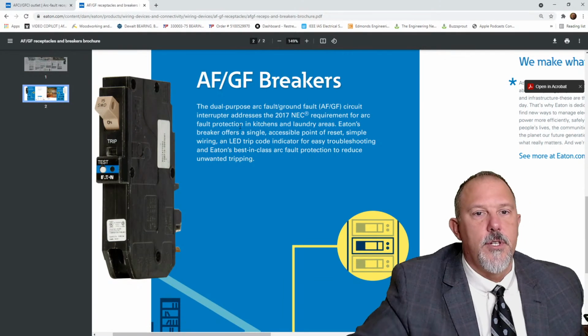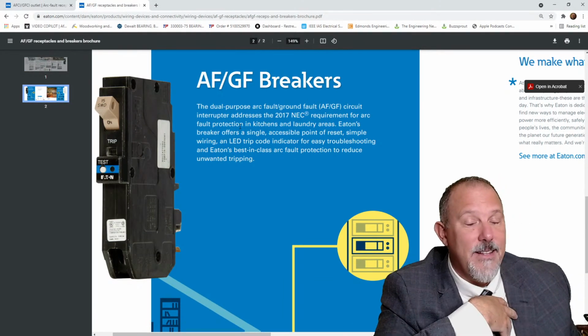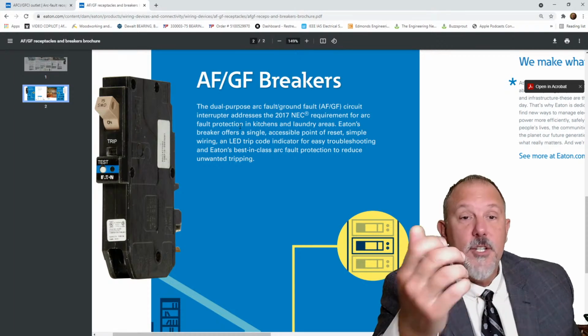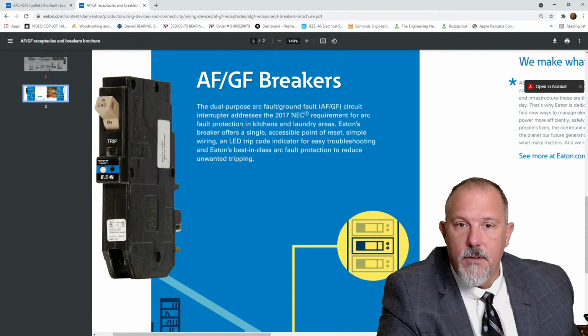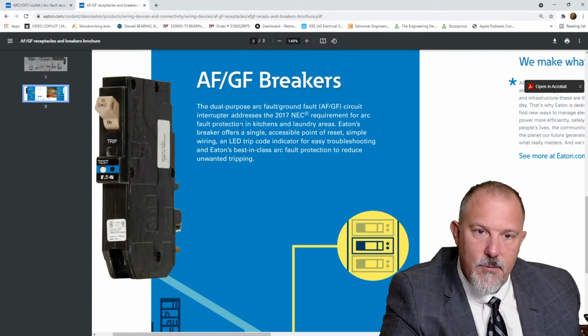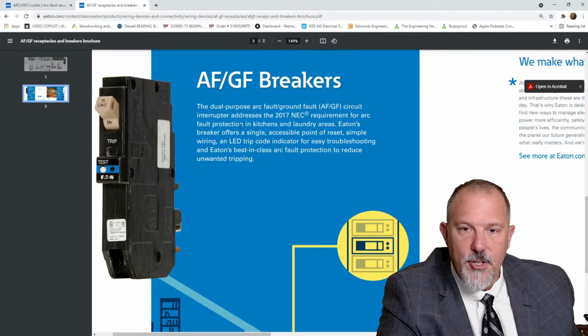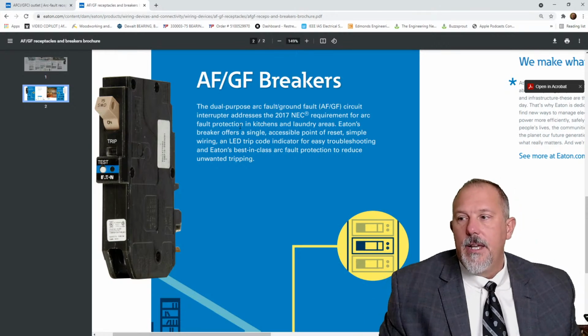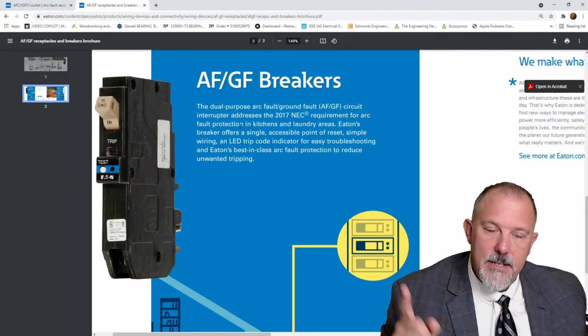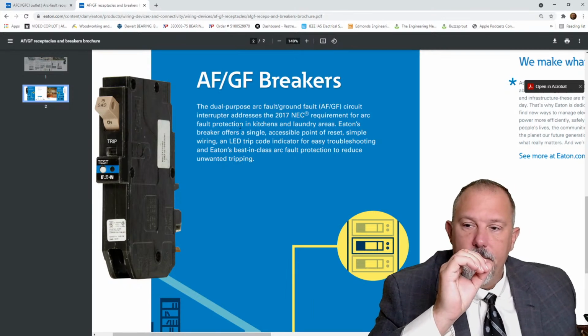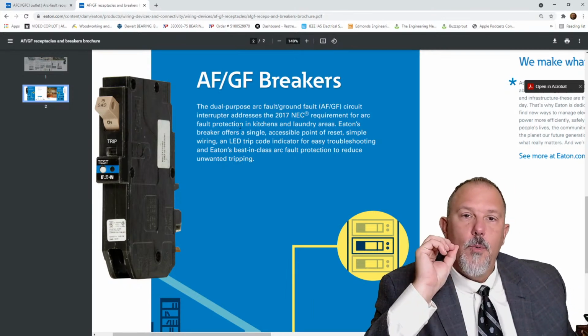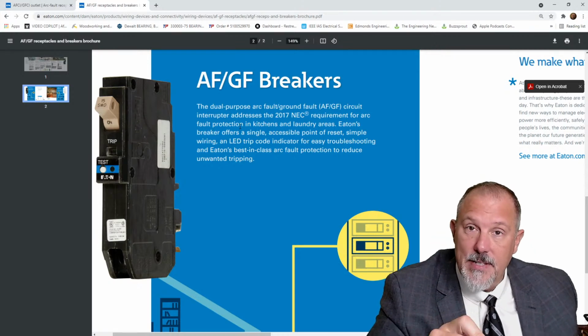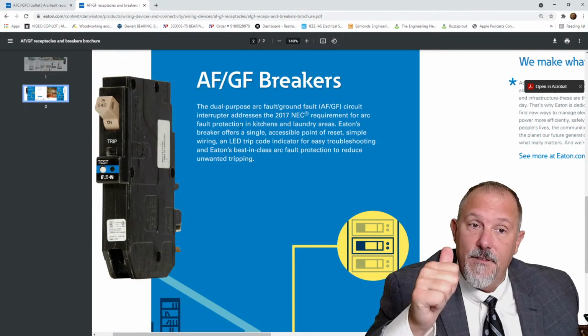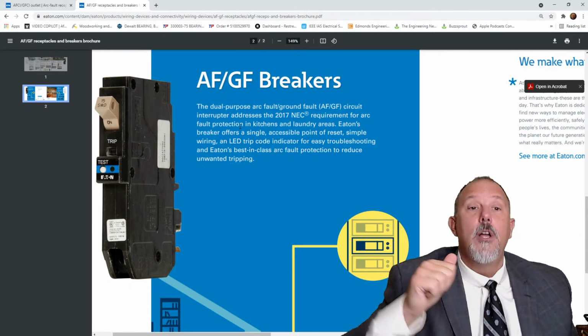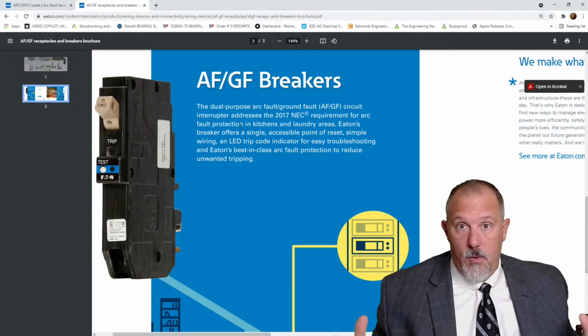AF/GF circuit breakers, the dual purpose. I lovingly refer to them as dual function, but a dual purpose arc fault, ground fault circuit interrupter addresses the 210.12 requirements. And look, kitchens and laundry areas, which is exactly what this question hones in on. This device is listed to UL 489, UL 943, UL 1699 for AFCIs. 943 is GFCIs and 489 is thermomagnetic circuit breaker. This thing does it all.